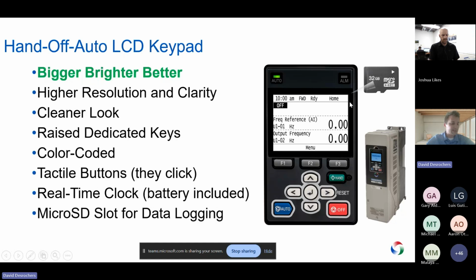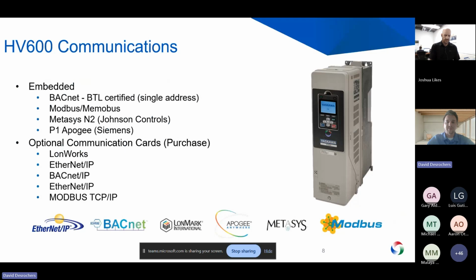And then we actually have a data logging feature, which is pretty cool. So I guess the takeaway here on HV600, this new lineup has significantly more intelligence within the drive, allowing you to rely less on external controllers and use more within the drive itself to accomplish what you're trying to do, whether that be PID loop control of a pump or a fan, or you just need to have a node on the network and be able to detect when there's torque coming from a motor. You can do both with the VFD. So along those lines of being able to have something on a node, the HV600 communication options are listed out here. So embedded, what comes right out of the box, we've got BACnet, Modbus, Metasys, Apogee. And then we actually have all of these Ethernet protocols that you can add on to the drive. And these are all available as standard options within our configured units.